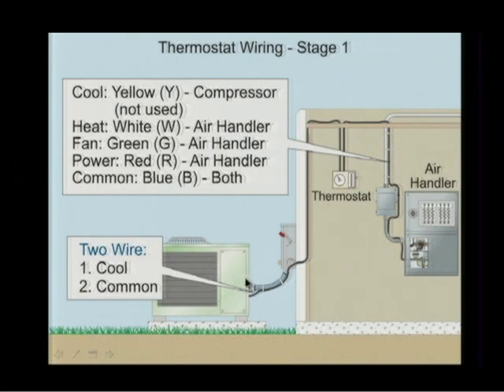Here's your compressor, and there's going to be a relay that's going to be operated by a 24-volt control, and I guess that'd be AC control. And then we have a thermostat. Then the air handler, in this example, would be, let's say, a heat pump only, without any supplemental heating. This is just on or off, so there's just one relay with a set of contacts. And then we have the heating element, which would also have a relay that will turn on the heating element. So that's one relay with 2 wires. This is the compressor with 2 wires.